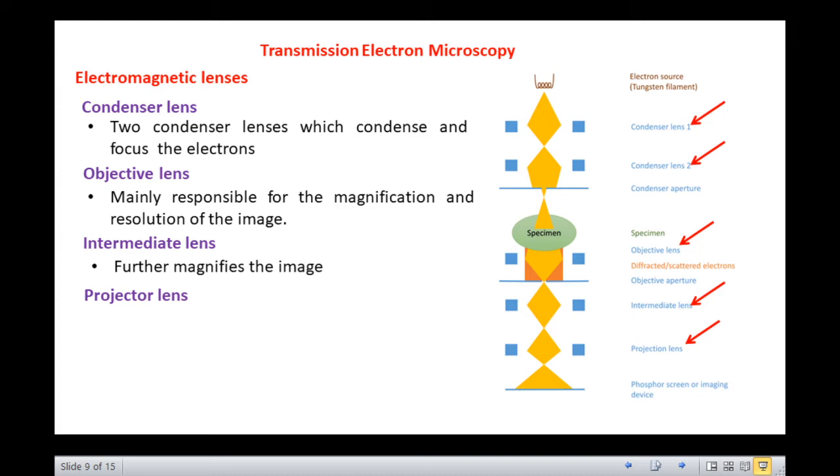Yet another electromagnetic lens in the TEM column is the projector lens. The projector lens projects the focused image onto the fluorescent screen at the base of the column or to a CCD camera beneath it. It converts electrons into photons. If you have been observing this figure, you can see certain apertures.